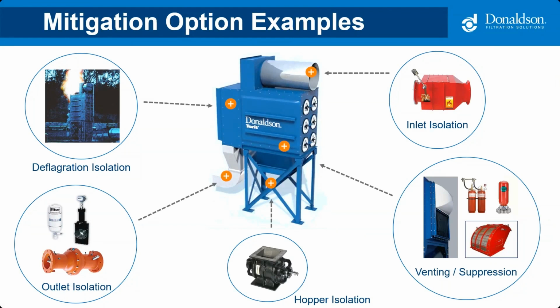Deflagration isolation. Our DFE collector was independently tested and the filters successfully isolated the deflagration and allowed no flame or sparks to pass into the clean air plenum. This is an important consideration when returning air back to a facility. Hopper isolation is typically a rotary airlock or a specially designed drum cover to prevent explosions from propagating through the dust collector hopper outlet. And then explosion venting on outdoor units and chemical suppression on indoor units help minimize or eliminate damage to the dust collector from an explosion before it becomes catastrophic. Again, this is a complicated topic, and if you have any questions, please reach out. We've got experts that can help.